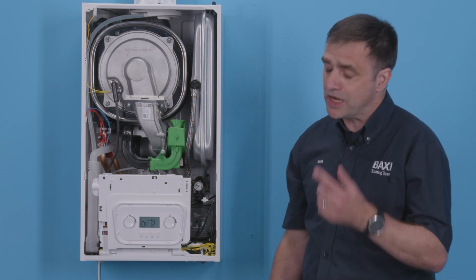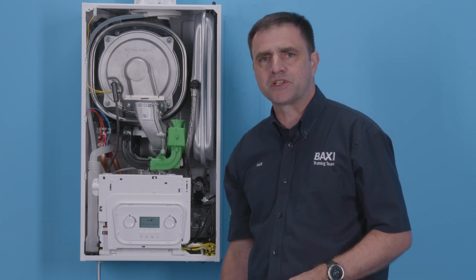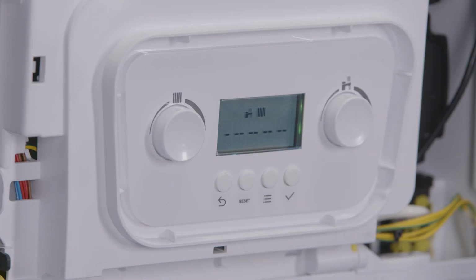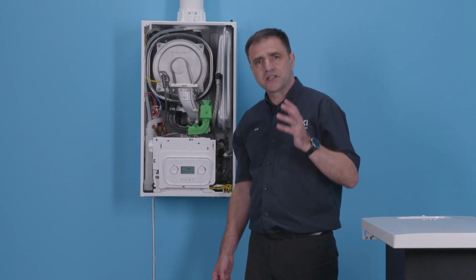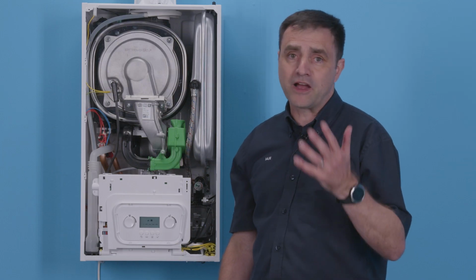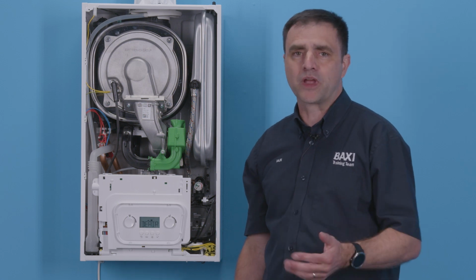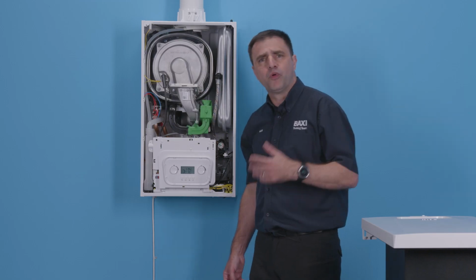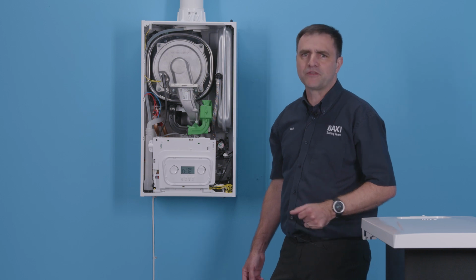Deaeration is important to clear all the air out so it doesn't damage the main heat exchanger. It will go down for about 5 minutes. The dashes will disappear over the 5-minute countdown. All you have to remember is to maintain the pressure. The diverter valve will move up and down and the pump will go on and off. Once it's all finished, the boiler will be in normal operation and you'll be able to fire it.